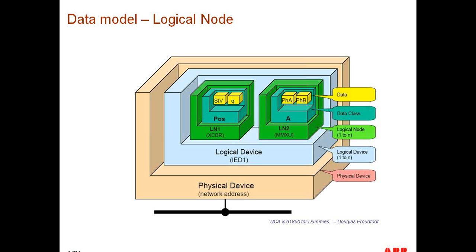And this is just a view of what I meant, or an expansion of what I meant, by logical node and the actual data model of IEC 61850. In 61850, we define a logical physical device. So in this particular case, this would be your relay. We could just make some examples. This could be an REL 670, or this could be an SEL 421, for example.